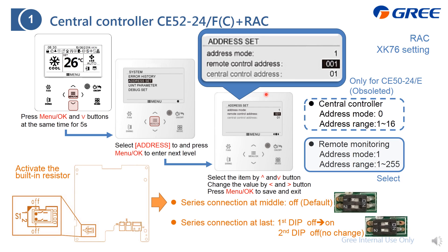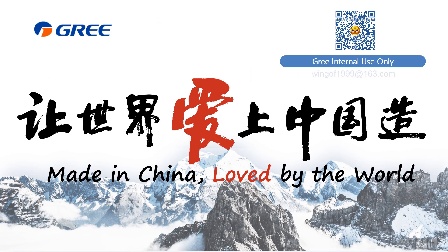Besides, if this wire controller XK76 is located at the last position, you also need to turn on the built-in resistor by changing the DIP switch located here. There are two DIPs — just change the first DIP from OFF to ON. Then you can turn on the built-in resistor to ensure proper communication. That's all for this part of the presentation. If you have any questions, please feel free to contact me on my personal email address. Thank you very much.